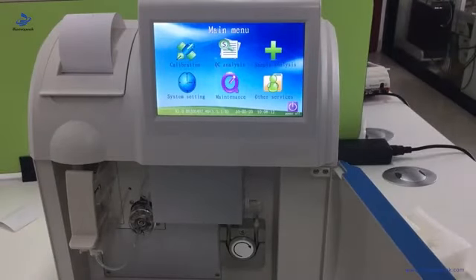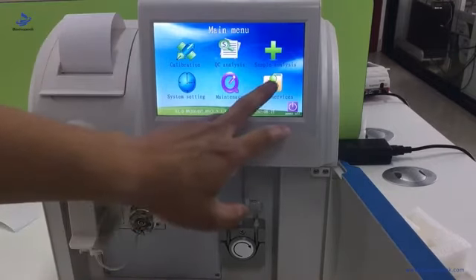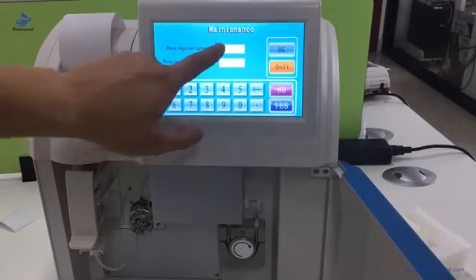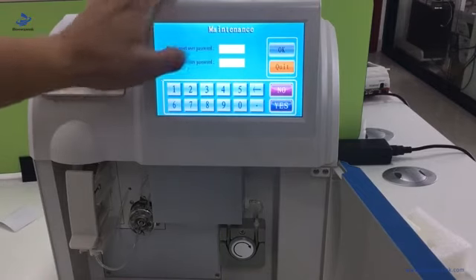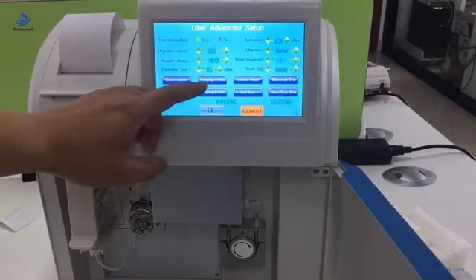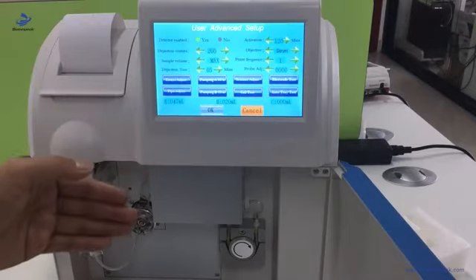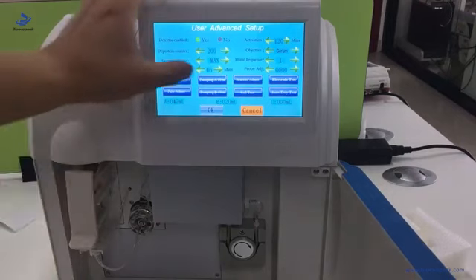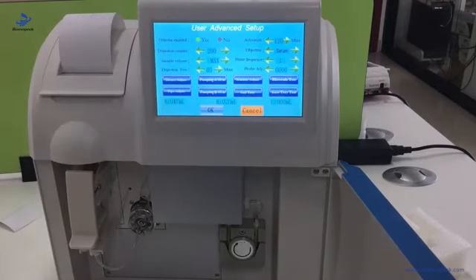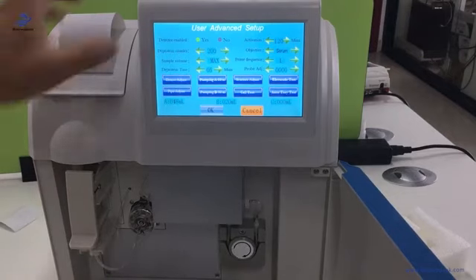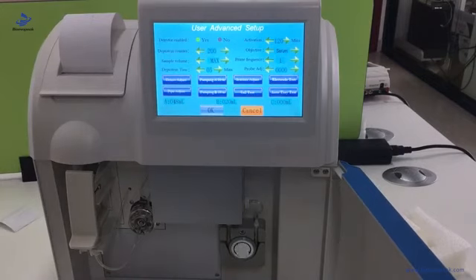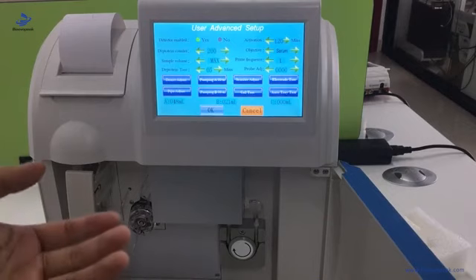Calibration. At first installation, the pipeline is empty, so we need to go to the other service, advanced setup, and here we put the user password 1 2 3 4 5 6 to get into the menu. Here we use pumping A times and B times to fill the pipeline. Then the calibration will be fine. Before your calibration, it is better to hit here 2 to 3 times to let reagents A and B fill the pipeline. When you are using this function, you can check the distribution valve to see if liquid passes through the pipe.